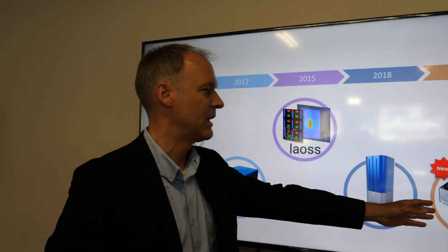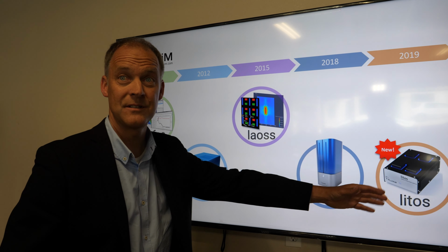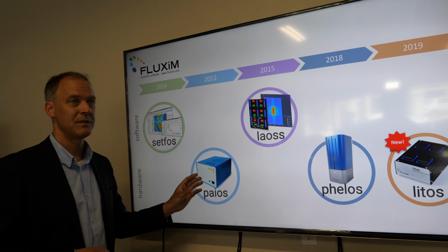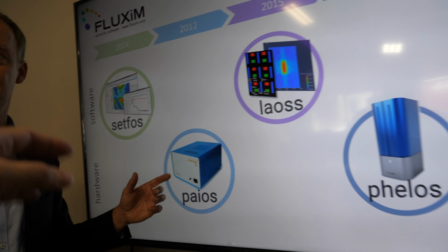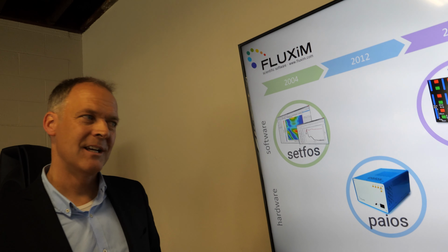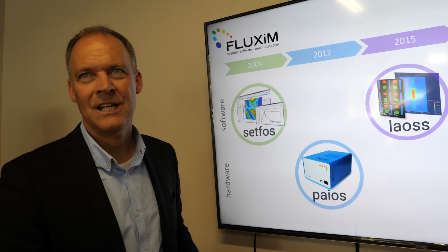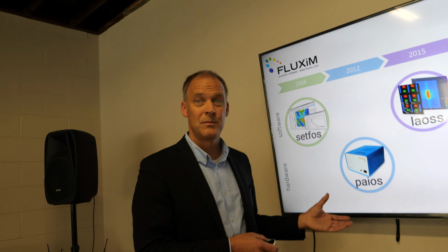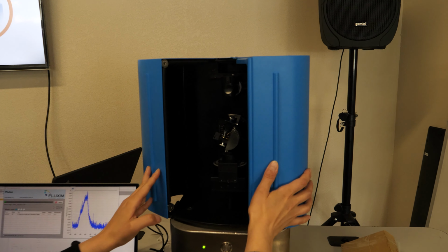So we want to let devices stress with this instrument and analyze with this instrument, which can measure JV curve, impedance, and transient. So each of these are totally different. You can't just have one that does everything. Yeah, but they nicely complement each other, and they all are operated by the same Fluxim characterization suite software.